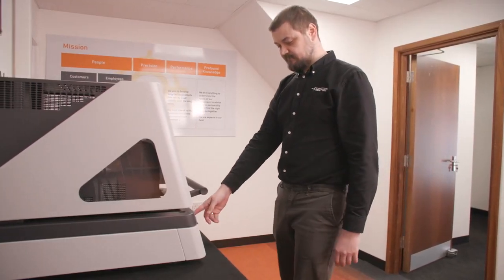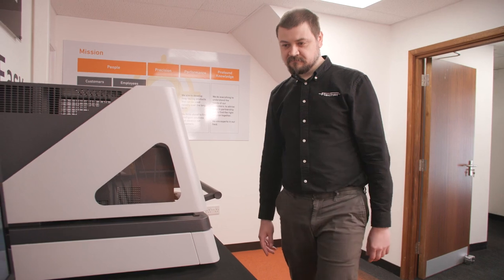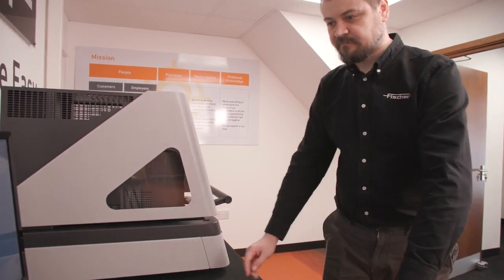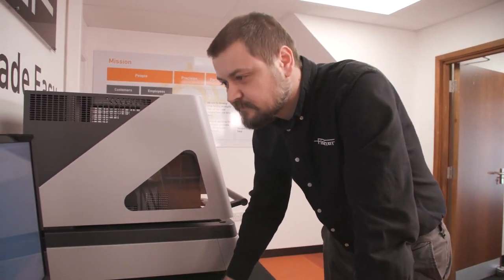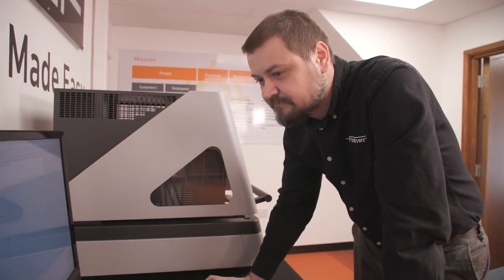In summary, the FischerScope X-ray XDLM237 is an easy-to-use, highly precise tool for automated measurements of thin layers less than 0.1 micrometres.